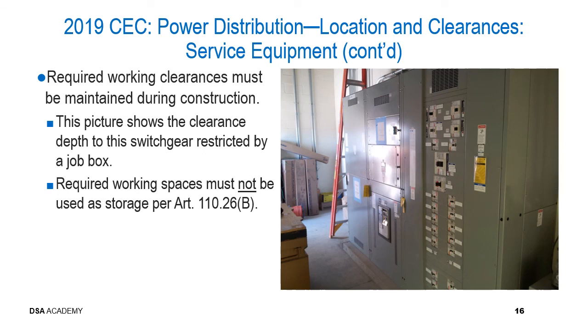This photograph shows an interesting situation that all project inspectors and contractors, for that matter, should be extremely concerned about and also aware of. And that is that even during construction, the required working clearances must be maintained. As you can see, if you look carefully in this picture, on the left-hand side, there's a job box where the corner is sticking out. Obviously, this job box is directly in front of this switchgear or this service equipment, and it does not appear that the minimum working clearance has been provided.